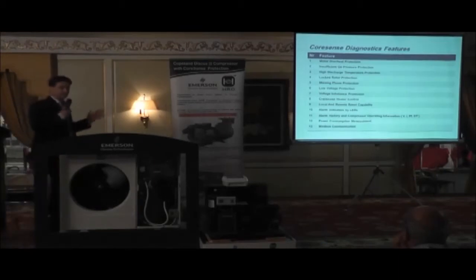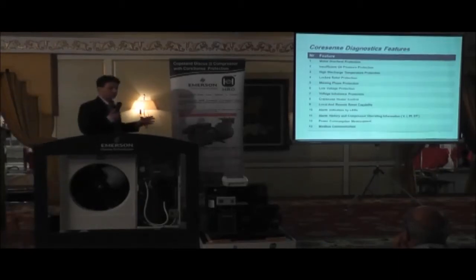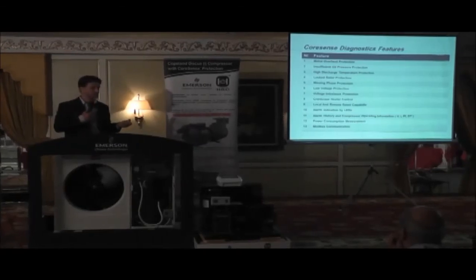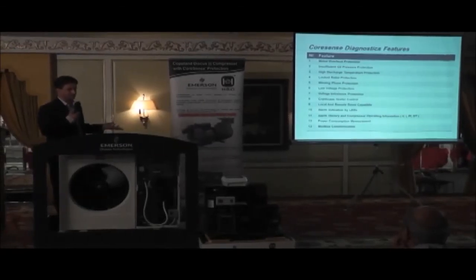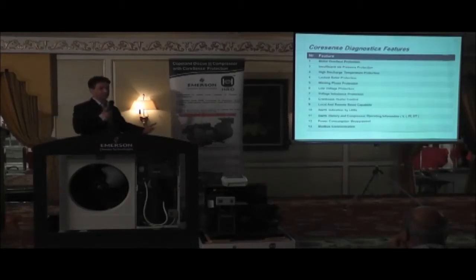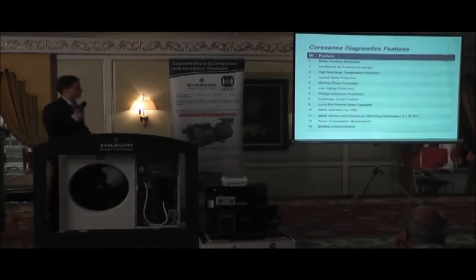So now typically before with Discus 2, you would have an oil pressure switch, whether you were using a mechanical one or the electronic one, and you had the INT69 thermistor, which is located in the motor box. Now with CoreSense Diagnostics, we are extending the safeties that we are now offering with the compressor. And these are indicated in this table.